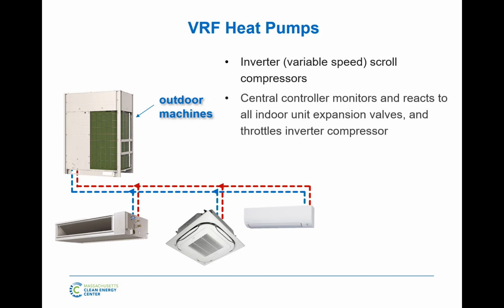What happens though is that this unit here, it's wired and it sees what all the different expansion valves are doing. So at any point in time, this guy out here knows that this one is asking right now for about 12% refrigerant. This one wants 30%. This one's at 60%. It knows exactly how much refrigerant is required. So the compressor, the VFD, or the inverter is going to ramp up and down to deliver the exact amount of refrigerant required at any point in time. Hence the name variable refrigerant flow. The outdoor unit varies the amount of refrigerant it delivers to the space in real time based on what the expansion devices are asking for.